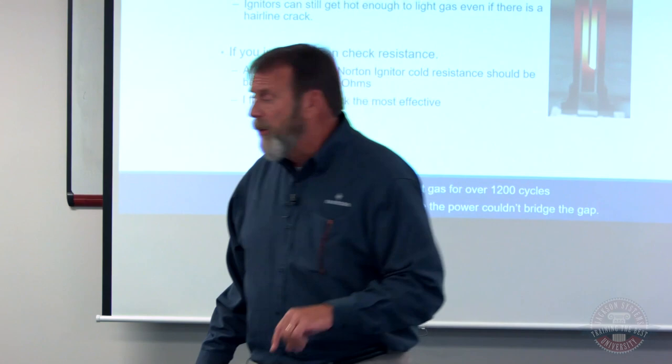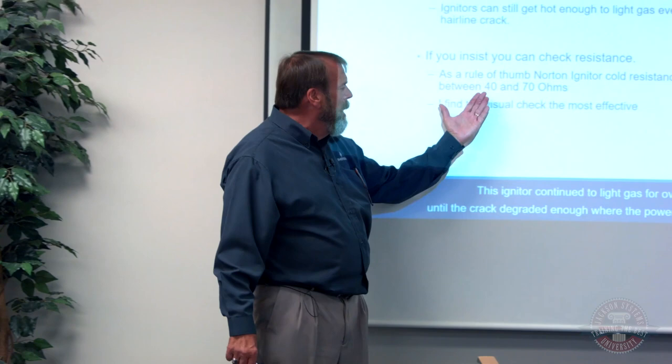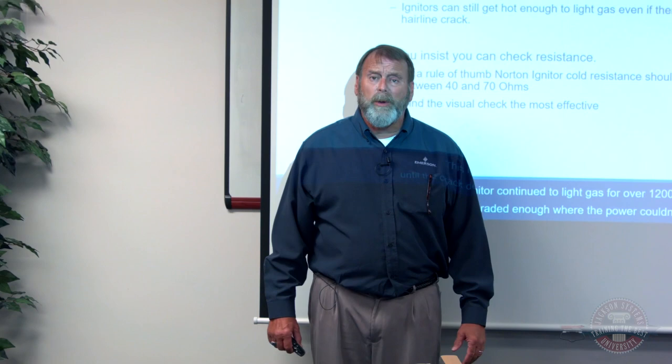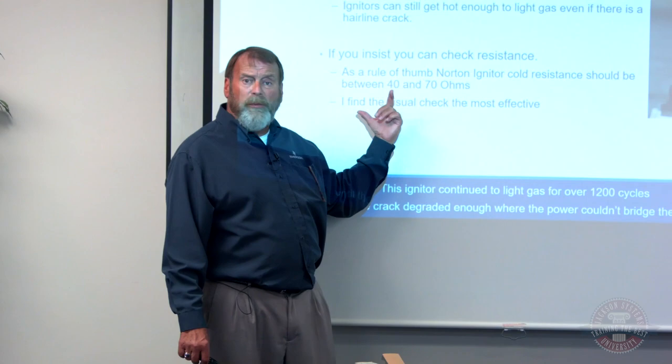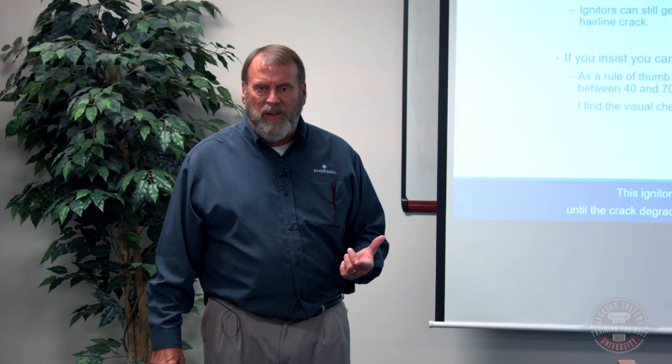Secondly, I have had innumerable people always asking me, can you check the resistance to see if there's a crack? Yes, you can. But I got to be honest with you, after doing this literally for 35 years plus, a visual inspection will tell me what's going on a lot quicker than cold-ohms, because I've seen below 40 and above 75 on a Norton-style silicon carbide igniter that have lasted many, many heats and seasons past the resistance when I checked it. You know, it's one way to do it. Personally, I look for a crack. So here's your first fun fact.